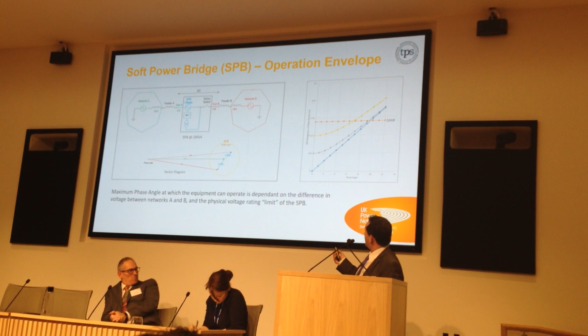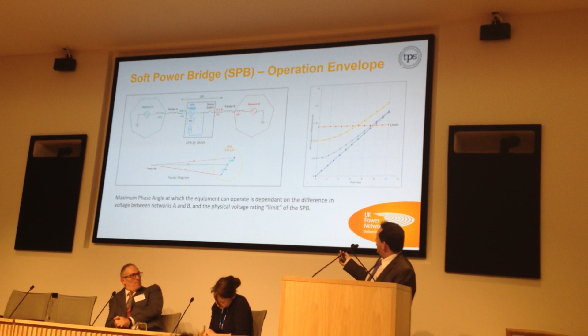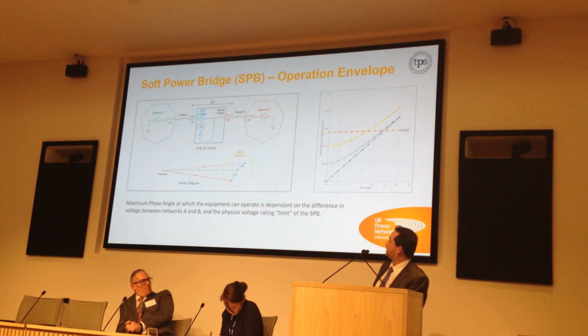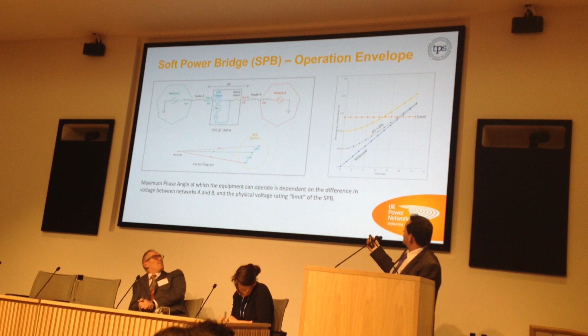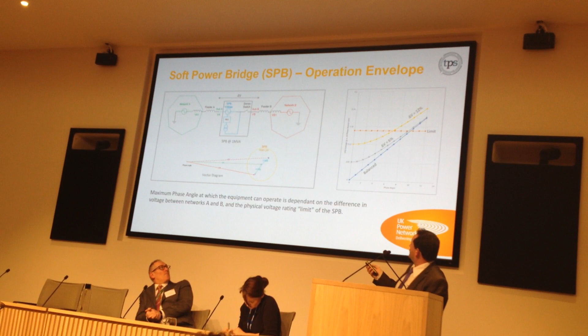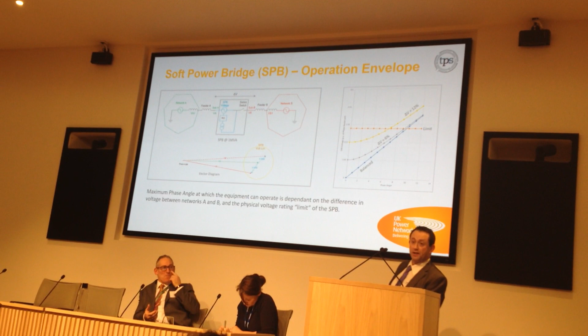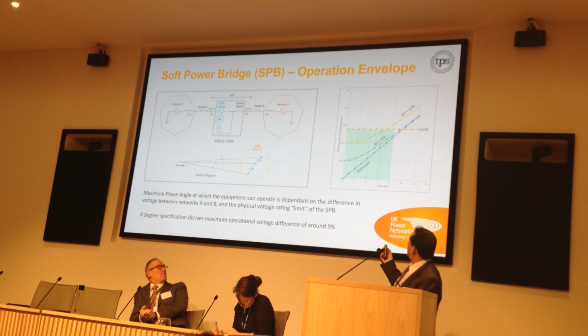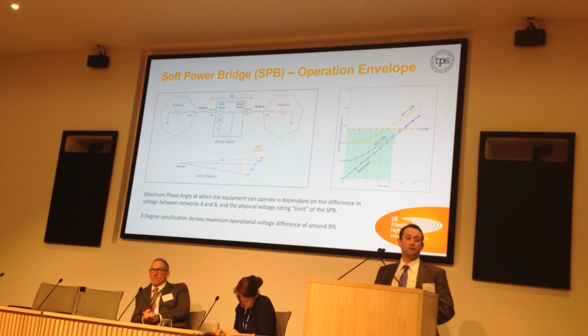So we have here a limit to the equipment. So this is a voltage limit that's applied to the equipment. Now if we put this equipment between the networks and the voltages are balanced, then where this blue line crosses this limit, that's our phase angle limit, which is approximately 10 degrees. As this becomes imbalanced, we've got a line here where we have a 6% voltage difference and we cross our limit at about 9 degrees. We go even further still, we get to a 12% delta and we cross at about 7 degrees. So where we set the specification, which was phase angle of 8 degrees, we're going to come in at around about 9% voltage handling capability, or the difference between the feeders.